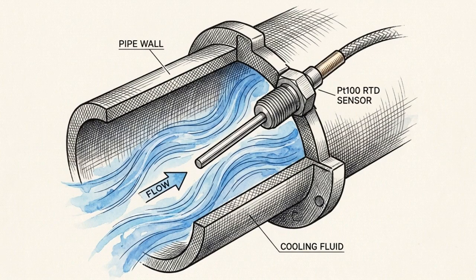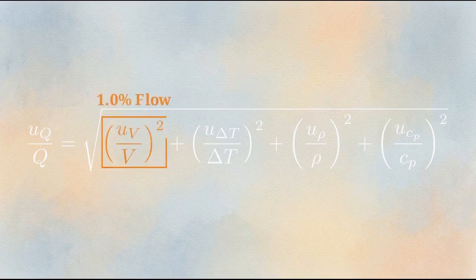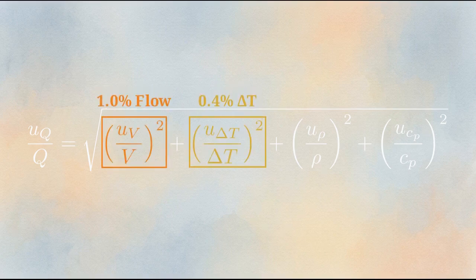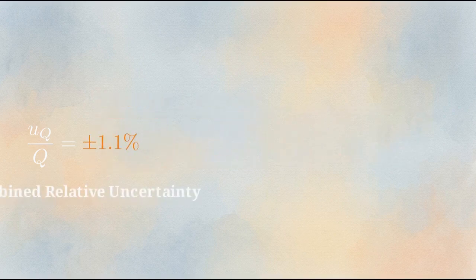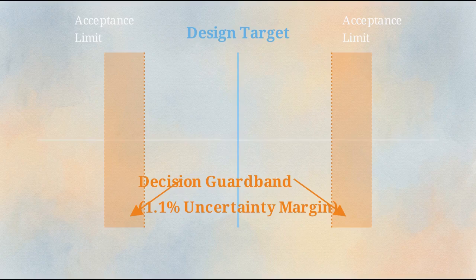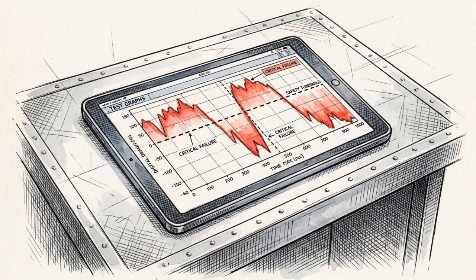to capture actionable data. This root-sum-square equation is the mathematical burden of proof for any heat balance experiment. Combining a 1% flow uncertainty and 0.4% delta T uncertainty mandates a strict 1.1% decision guard band for all accepted results.